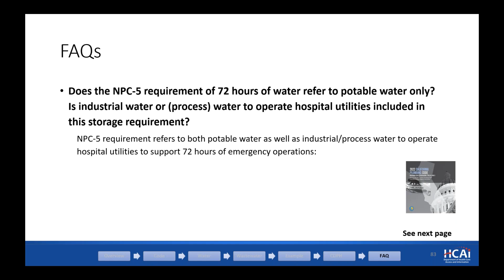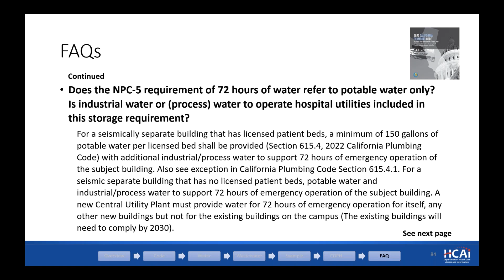For seismically separate buildings, there is a minimum requirement in the code of 150 gallons per bed for the 72 hours. There are exceptions, and when there are no licensed beds, as we talked about for the central utility plant, then it must provide water for 72 hours of emergency operation for itself or any other new buildings, but not necessarily for the existing buildings on campus, because those need to comply by 2030. Of course, you can do it sooner, but the deadline is 2030.